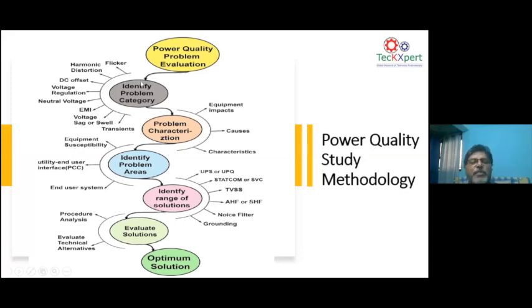It is not that all power quality problems are harmonic problems and all power quality problems are solved by an active harmonic filter. No, this is a normal trend. I know in industry many people do this. If it's a transient problem and some electronic card fails, somebody will say it is a harmonic problem. Or it could sometimes be a noise signal, because a lot of electronic devices produce noise. If your grounding is not proper, naturally these noises will pass through the ground and come towards the power side, and it can cause failure of electronic cards because the reference voltage of the card will get affected and the card will fail. But then sometimes people say it is harmonics.